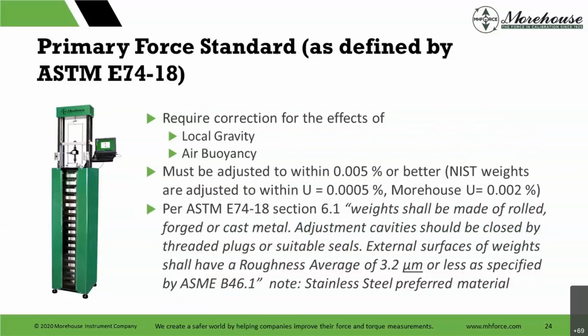Rolled, forged, or cast metal adjustment cavities should be closed by threaded plugs or suitable seals. External surfaces of weights shall have a roughness average, and it goes on. So that's basically saying, hey, I have a weight here. And for those that are auditors and the like, if you run into a company that's using mass weights to do force calibration, the main important thing is to ask how you are correcting those weights for force. Are you correcting for local gravity? Are you correcting for air buoyancy? What are the error sources?